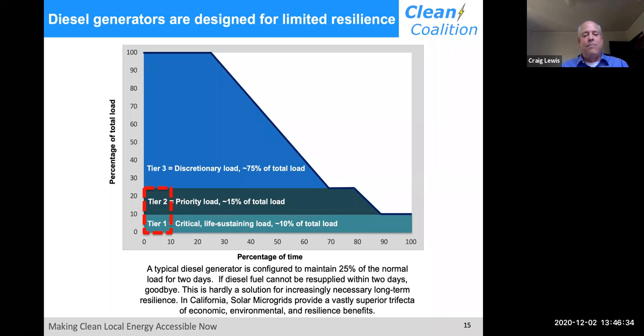I want to debunk the myth of diesel generators. They're unfortunately the de facto resilience solution nowadays, but they're only designed to keep about 25% of the loads, generally tier 1 and 2 together, and they usually have 2 days of on-site fuel supply. After 2 days, you're done, lights out, everything's off. Diesel generators provide far less resilience compared to solar microgrids, which should really be the de facto approach for resilience.